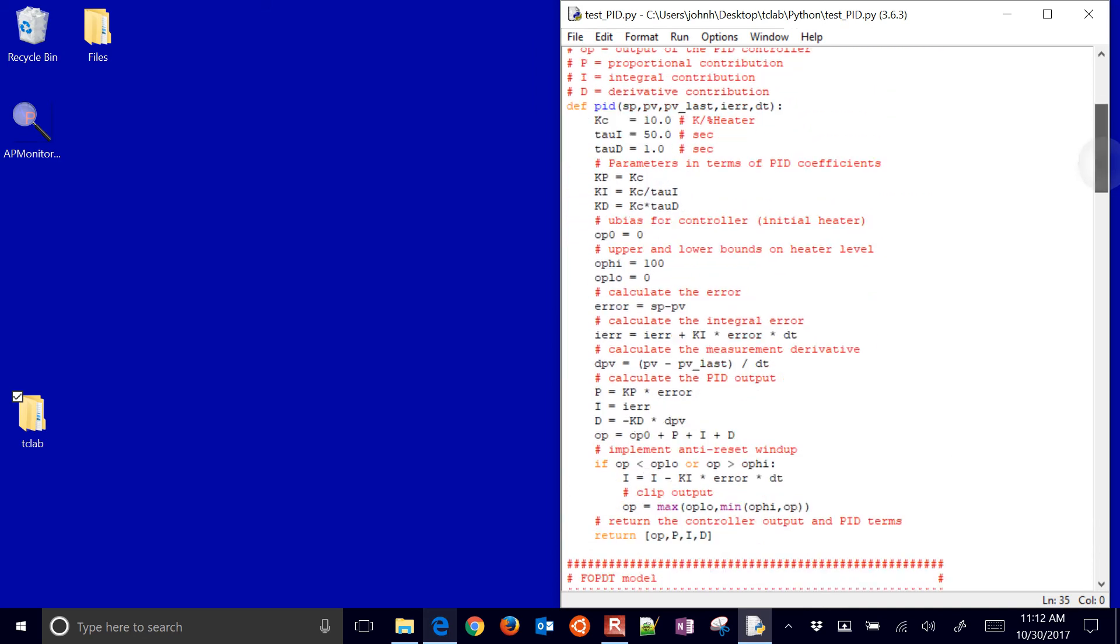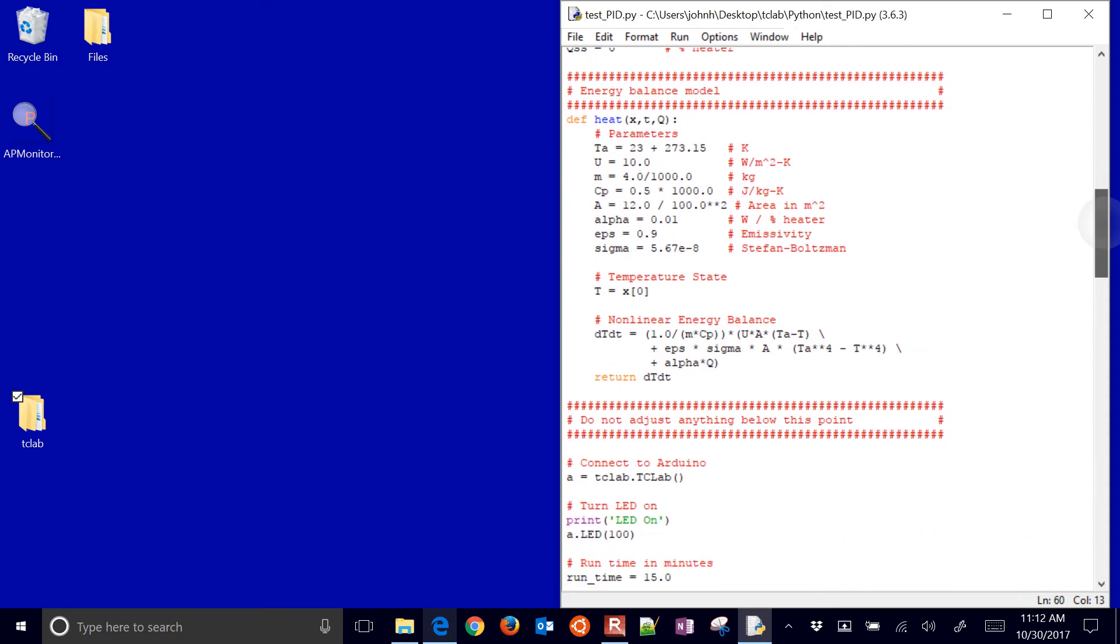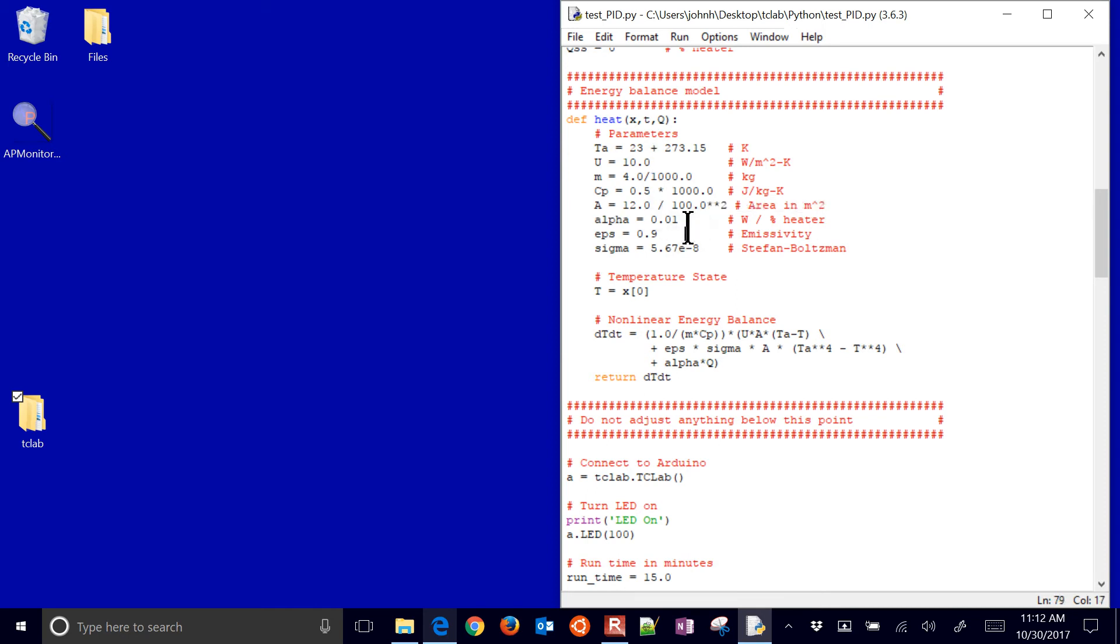And then if we scroll down just a little bit, we'll see our models. Here's our FOPDT model, right here, the first order plus dead time with a Kp, Tau p, and Theta p. And then also my energy balance. So here are some parameters, like U is one of the unknowns, and then Alpha is also one of the unknowns. So plug those in after the parameter estimation, and then it'll be able to track it.